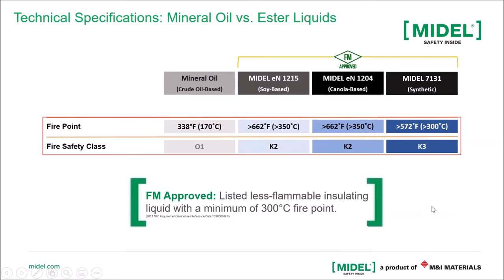And that's when you get what's classified as K class, fire safety class. You'll see mineral oil is O class, which really O should stand for zero because it's not very fire safe at all. And then on top of the K or the O, you see a 1, 2, or a 3.